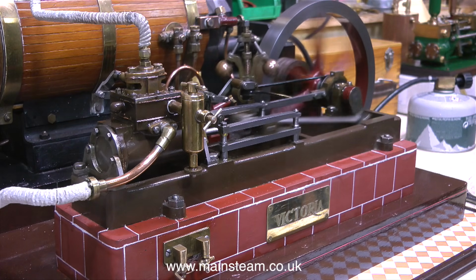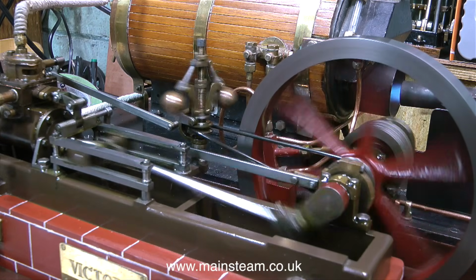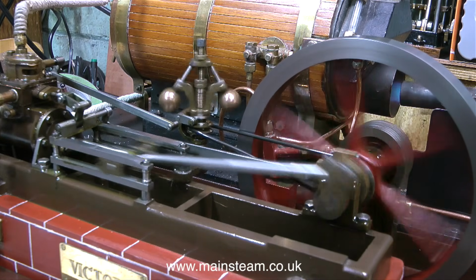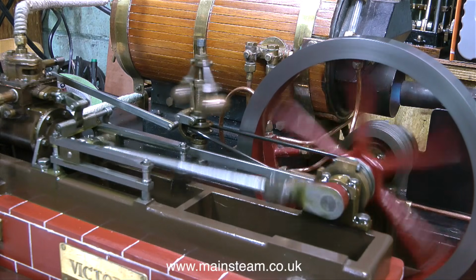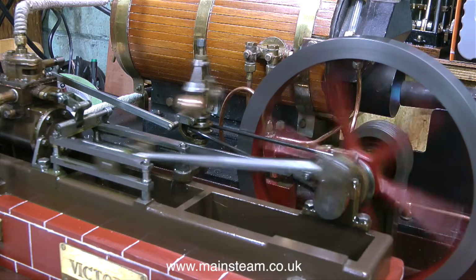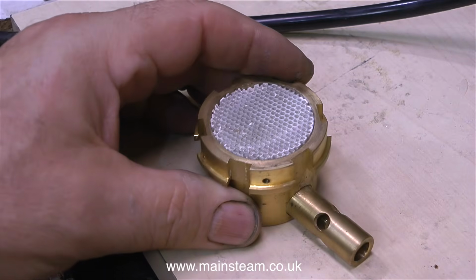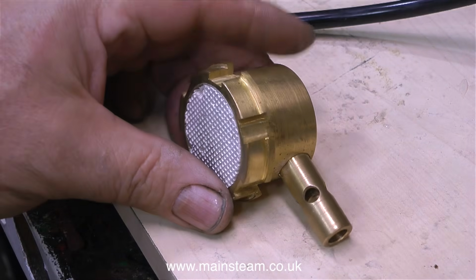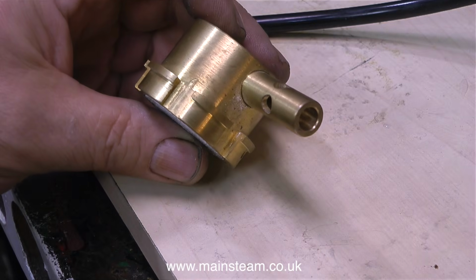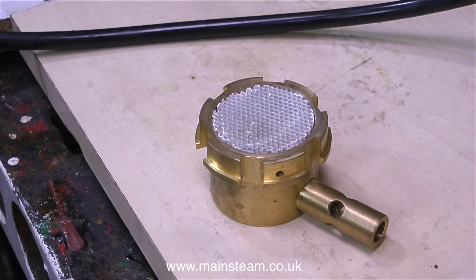Ceramic burners make an entirely different type of noise. They set up a resonance down the centre flue, and the centre flue becomes a musical instrument that generates a really bad howling noise. Plus certain types of ceramic burner actually burn out. One exception to the rule was a type that Mike Abbott at Max Steam used for a while. These burners didn't seem to howl hardly at all, but they did have a problem. The gas would suddenly start burning inside the burner and cremate the ceramic.